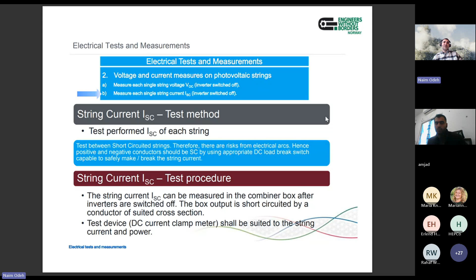So the comparison is the same as for VOC. You take the records for the short circuit current for the first string, second string, third string, and so on, then compare them. If the differences are within plus or minus 5%, that's okay, meaning all are healthy. If any reading is higher or lower than this range, something is wrong, so you need to investigate, check the connections, and so on.